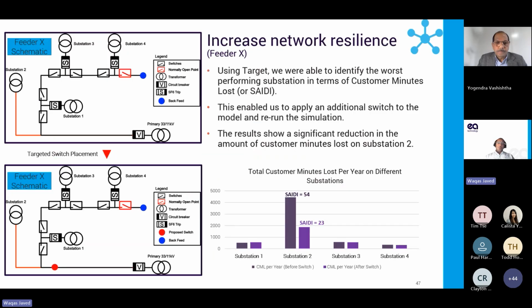So what we did, after identifying substation 2 as the location with the highest customer minutes lost, was test a targeted intervention to see how much improvement could be achieved. Using the target model, we added a single additional switch at a specific point on the feeder, just before the section that feeds substation 2. This was a low-cost intervention, but one that had a significant impact on restoration pathways during fault conditions.